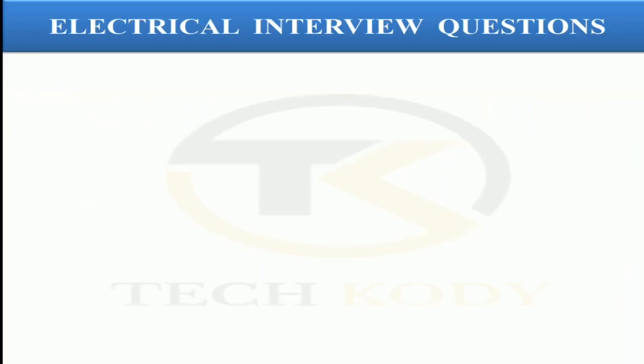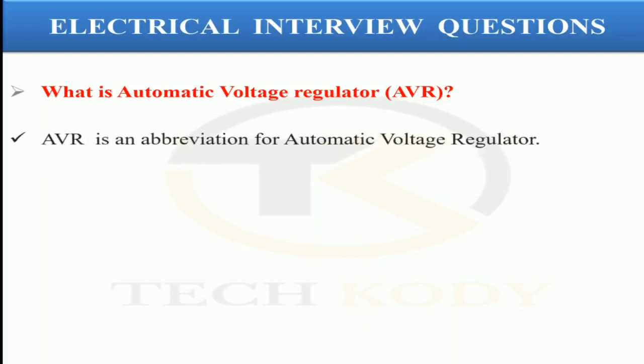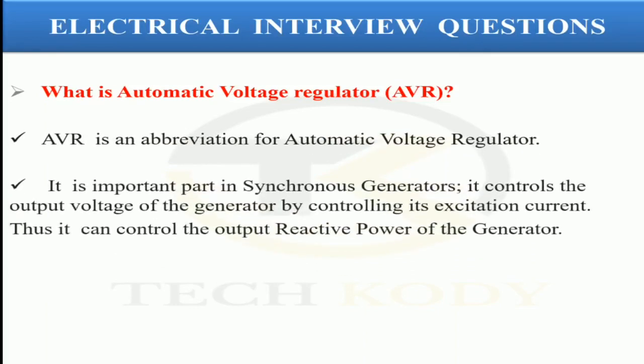The next question is: what is an automatic voltage regulator? The automatic voltage regulator is the heart of the synchronous generator. It controls the output voltage of the generator by controlling its excitation current. Thus, it can also control the output reactive power of the generator.